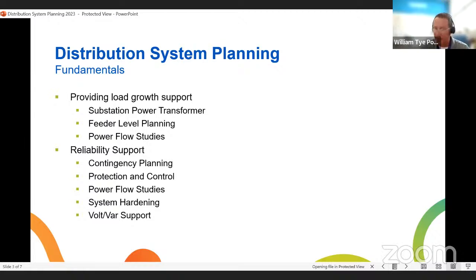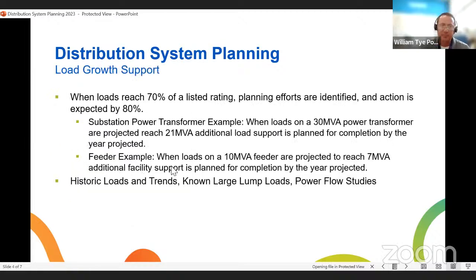Our fundamental load growth planning is that we plan to a 70% threshold. So what that means is that when loads reach 70% of a listed rating, our planning efforts are identified and actions are expected to be complete by the time we reach 80%. After we go beyond that 80%, we're out of the planning efforts and we're more into urgent system support needs. So a lot of those efforts don't end up in this portion of our planning activity.